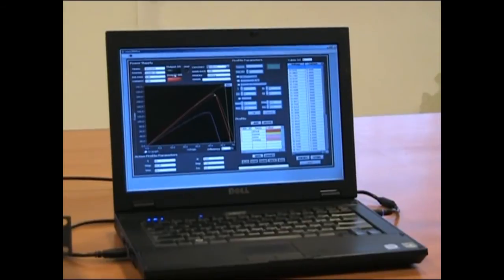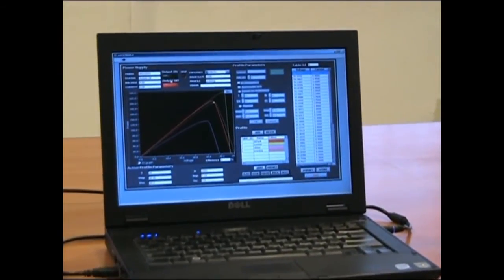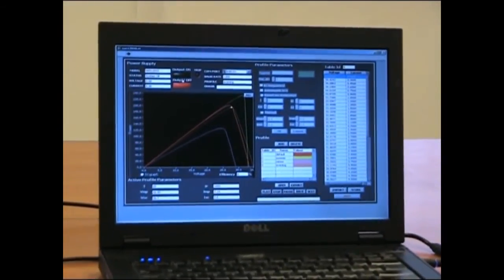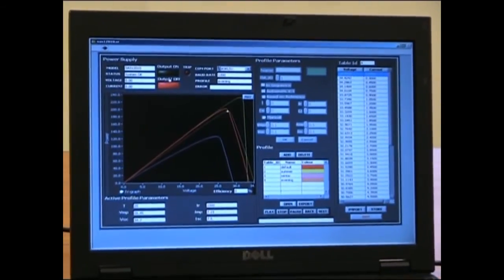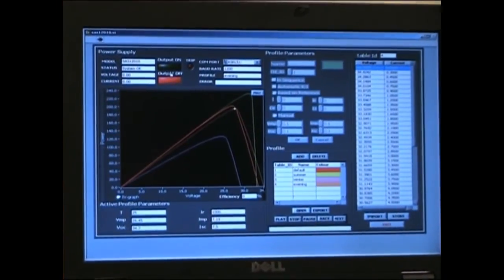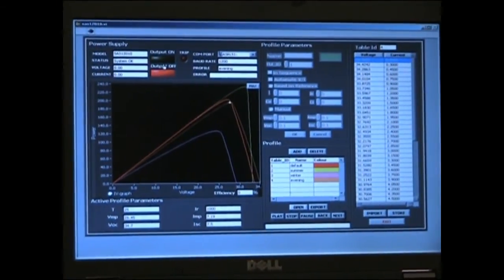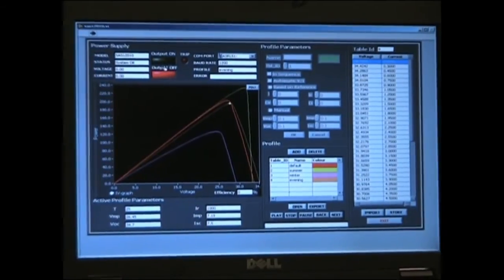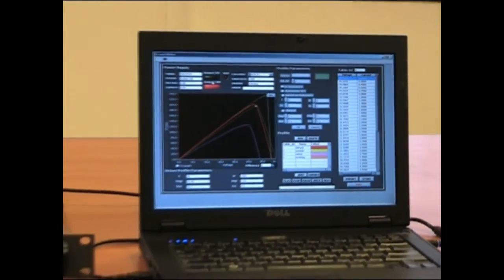The soft panel can automatically simulate any curve profile based on user-defined points. The profile can be exported to SAS 12010 via any communication interface like LAN, GPIB, USB or RS-232.